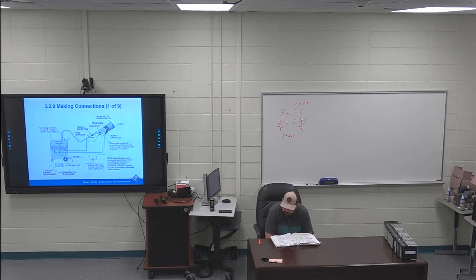For example, a tester rated at 75,000 volts at 2.5 milliamps can deliver the following output power. 75,000 volts times 2.5 milliamps is 187.5 watts. And then 187.5 watts times 1.3 is 243.75 watts. So that's where it's saying that the factor should be about 1.3, is what you want to know.